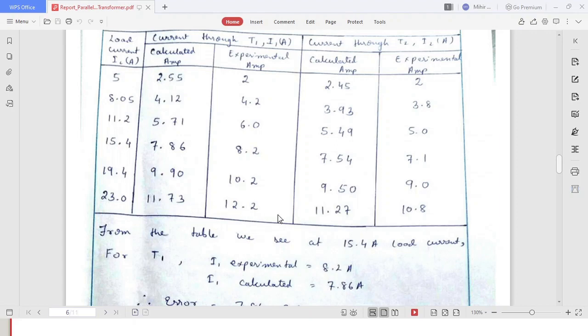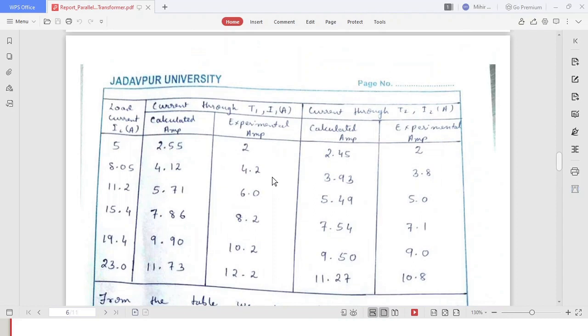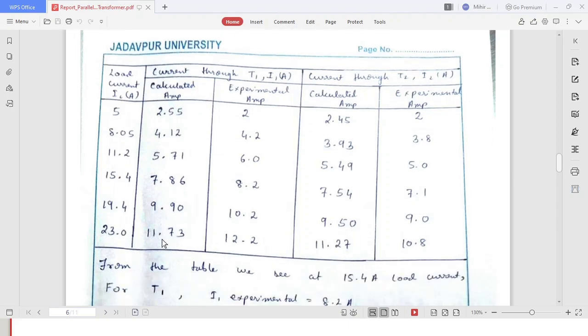One thing you must keep in mind, the loading of the transformer must not exceed its rated loading. Here the secondary side voltage is 220 volt and the rating is 3 kVA, so its current rating will be around 27 ampere. 13.7 multiplied by 2, the total load current is this 27 ampere, and individual transformer loading will be simply 13.6 ampere.